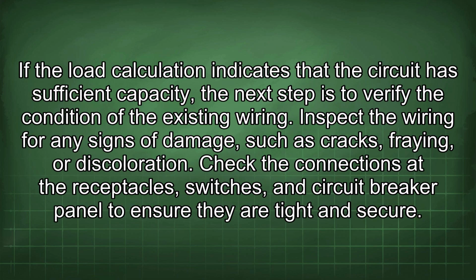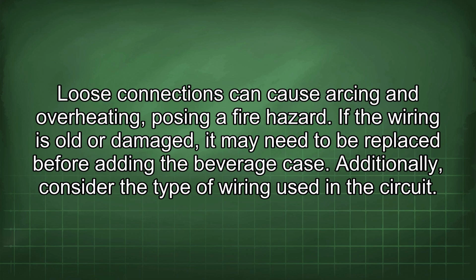If the load calculation indicates that the circuit has sufficient capacity, the next step is to verify the condition of the existing wiring. Inspect the wiring for any signs of damage, such as cracks, fraying, or discoloration. Check the connections at the receptacles, switches, and circuit breaker panel to ensure they are tight and secure. Loose connections can cause arcing and overheating, posing a fire hazard. If the wiring is old or damaged, it may need to be replaced before adding the beverage case.